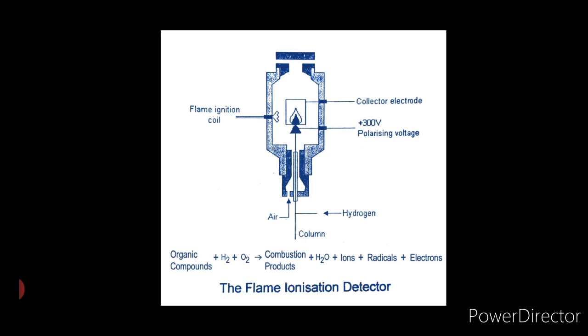A wire loop ion collector collects the charged particles and produces an electrical current which is fed into the printer. FID is sensitive only to oxidizable compounds and does not respond to water vapor or carbon dioxide. Since the detector response is proportional to the amount of organic material in the carrier gas, quantitative analysis can be done.